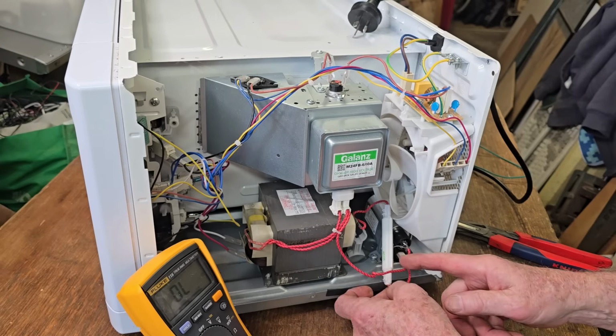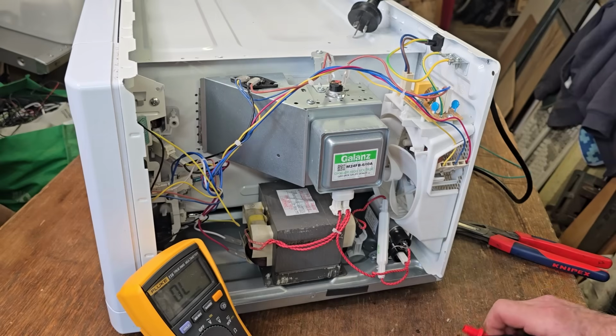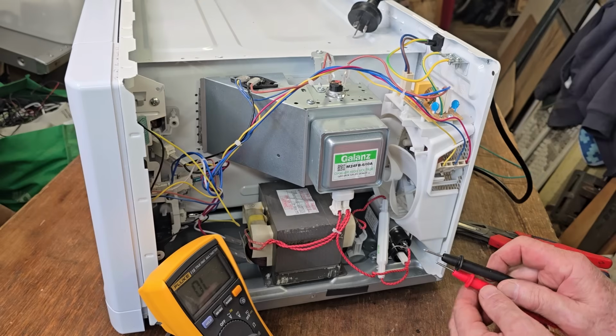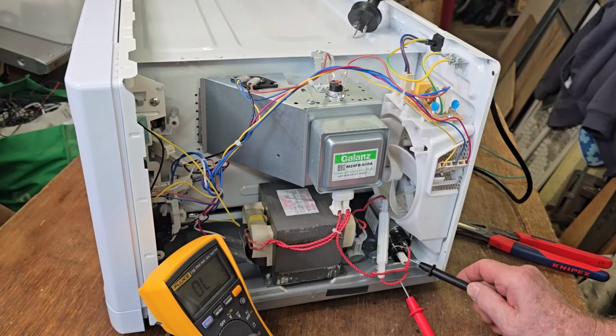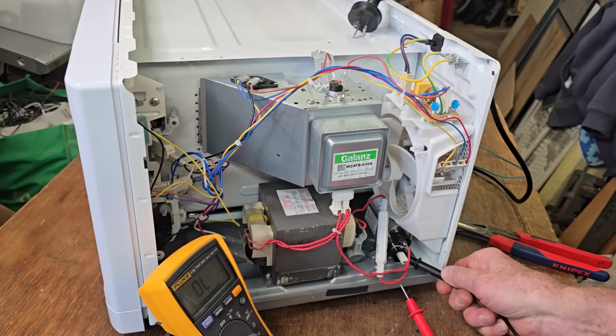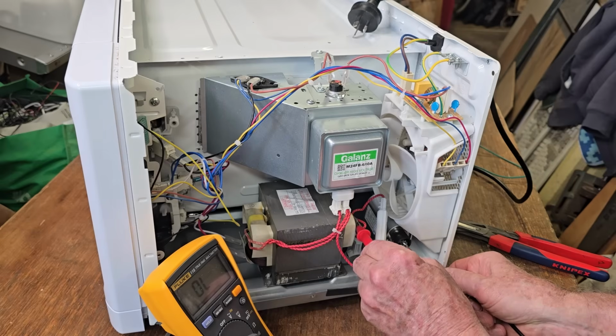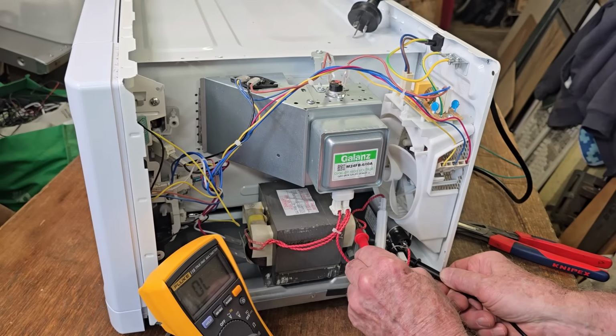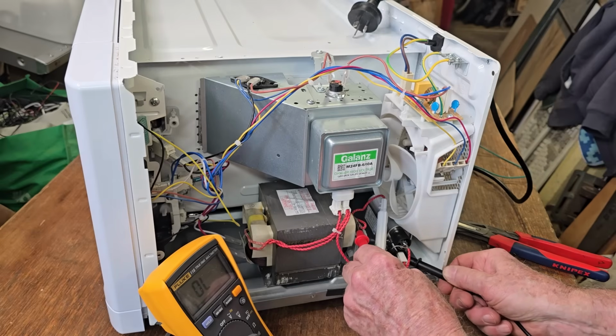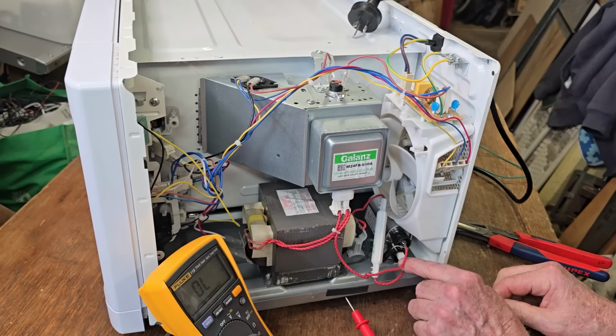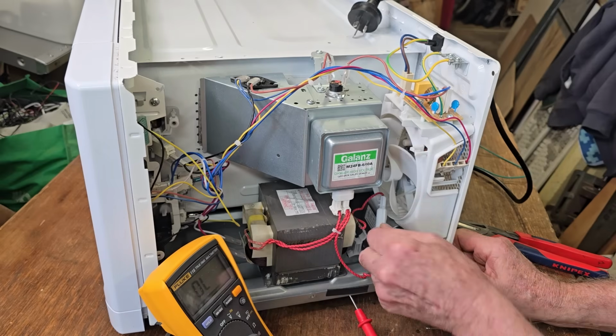If there's something wrong in the high voltage section, that will probably blow. We still have our meter on continuity, so we can check whether we have any continuity through the fuse, and we have nothing. So let's take that one out, because that's blown.